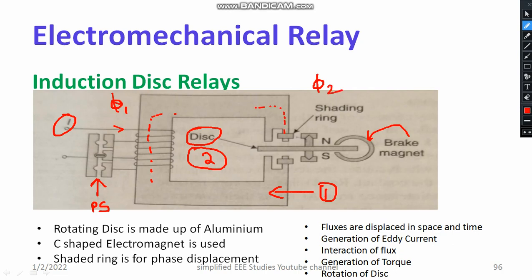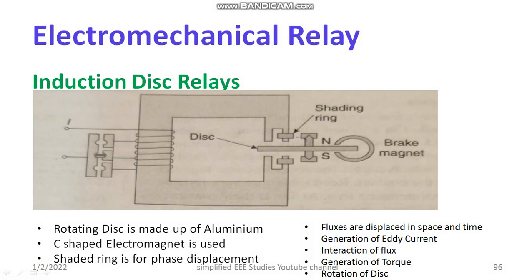Both fluxes will be out of phase. Due to the difference in flux, torque is produced at the aluminium disc, and thereby the aluminium disc starts operating. If the aluminium disc needs to be held in a desired stationary position, brake magnets are employed. This is how the induction disc relay operates.